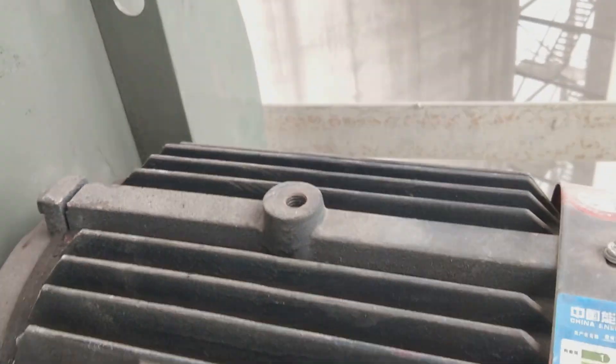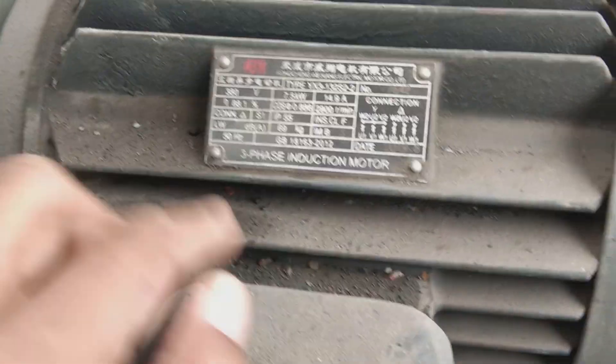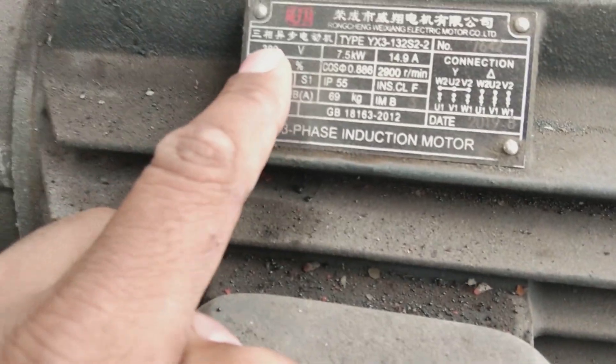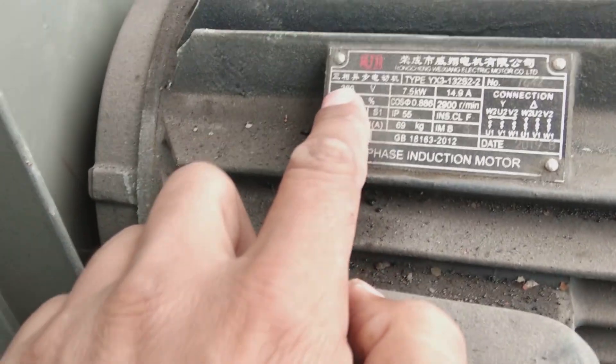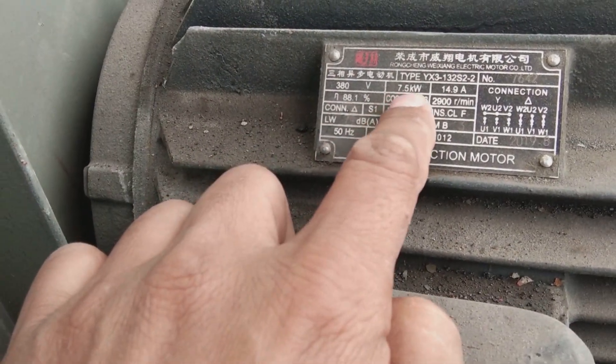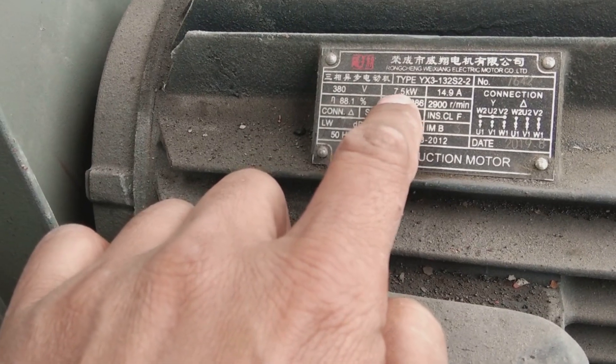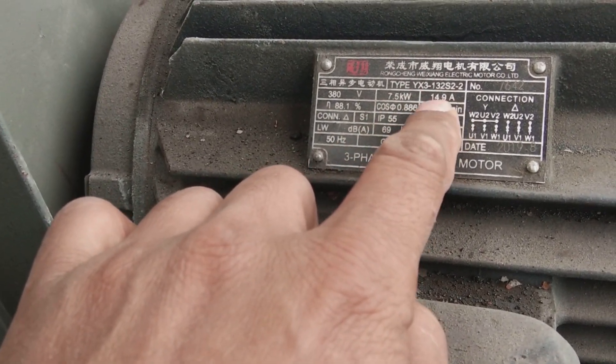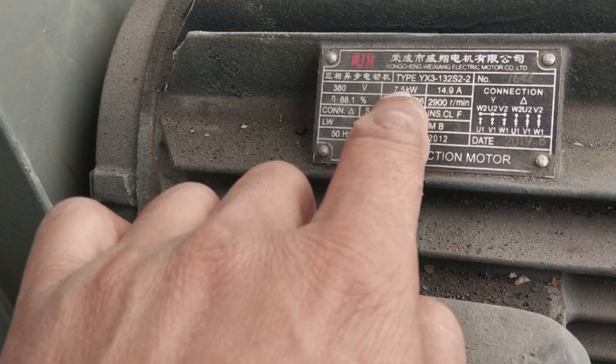Here's the motor part, which is electrical. This is a 380 volt low voltage motor, and it's star or delta connected. This is 7.5 kilowatt, and 14.9 ampere is the current.